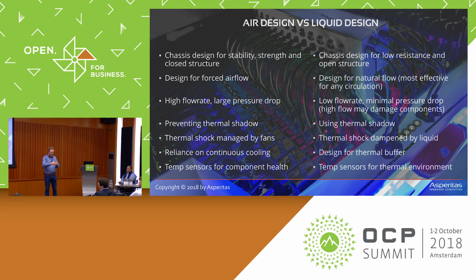Thermal shadow: two CPUs sitting behind each other, where the first CPU is actually preheating the air that goes into the second CPU. That can become a very big design challenge when designing a chassis for air. Within liquid, that effect is greatly reduced, because the thermal upgrade of that bit of liquid passing through the first CPU is not so much, so the second CPU doesn't have a very big temperature difference compared to the first. You can actually use that in the design of a mainboard or a chassis.